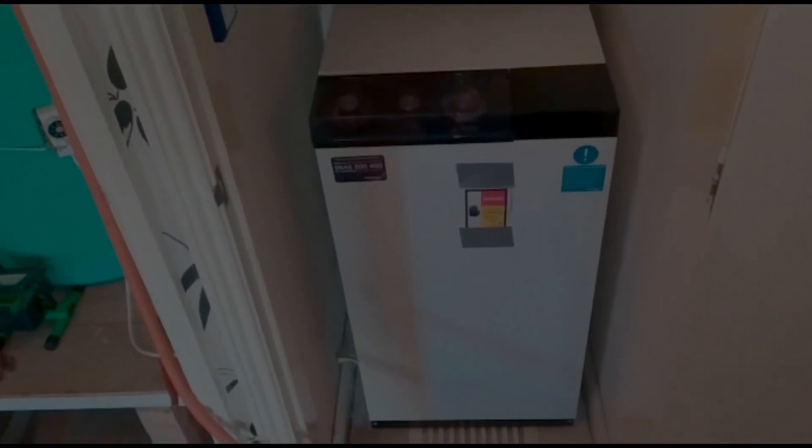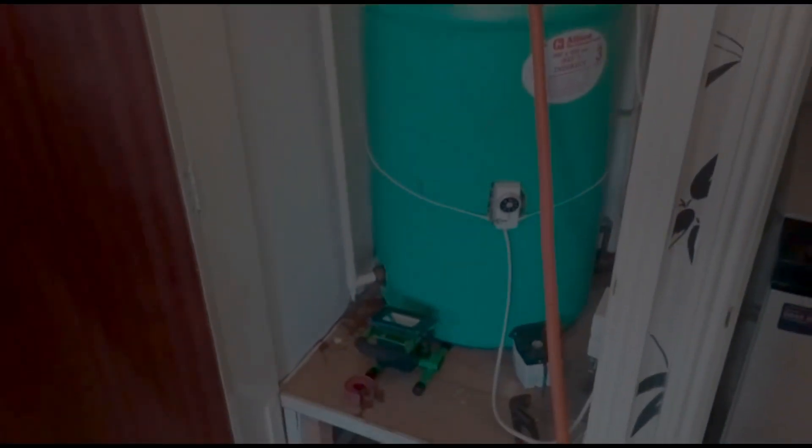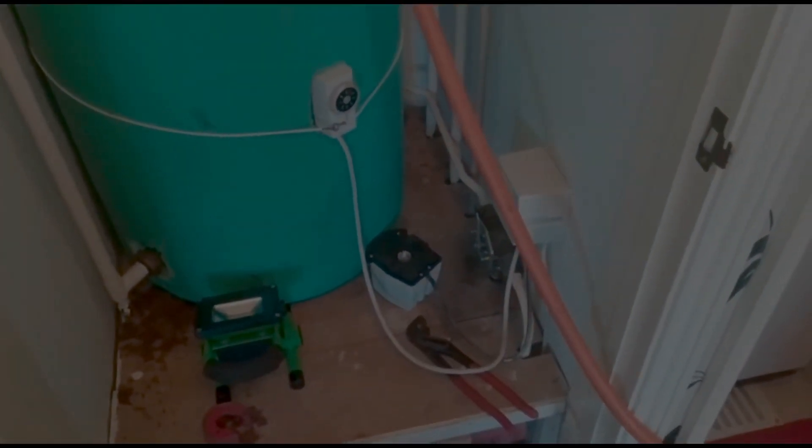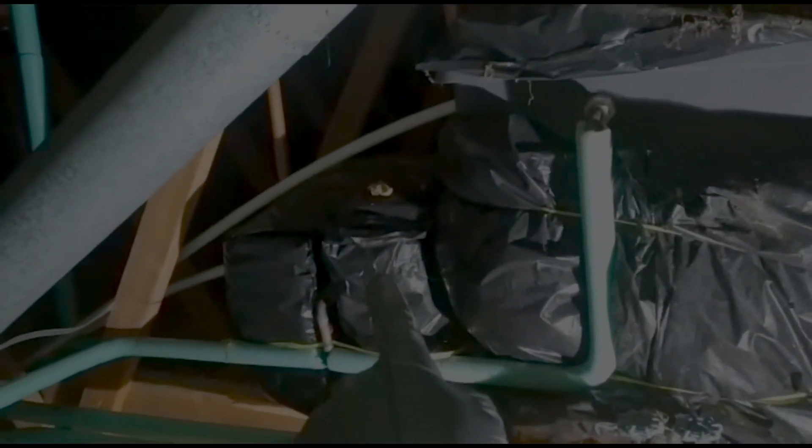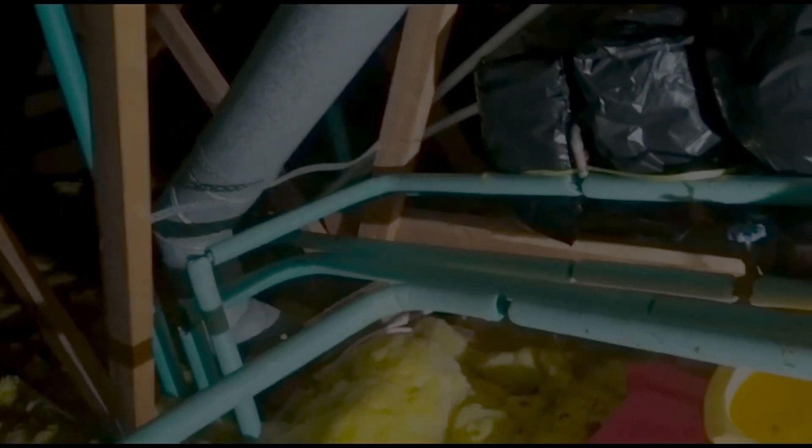Today's job is Monday. Floor standing boiler out that's been condemned. Flue system out. Hot water cylinder out, which we're just draining out at the moment. Get rid of all this nonsense, we're changing it over to a combi. The customer wants a combi in this property. We're going for quite a large combi because there is a bath and a shower above it and a separate shower and four people living here. Tanks in the loft space here. Beautiful old valves. Blue ones, look. The right colour. It's great, isn't it? So, cold water storage system. F&E tank. That'll all be coming out. All this will be coming defunct.